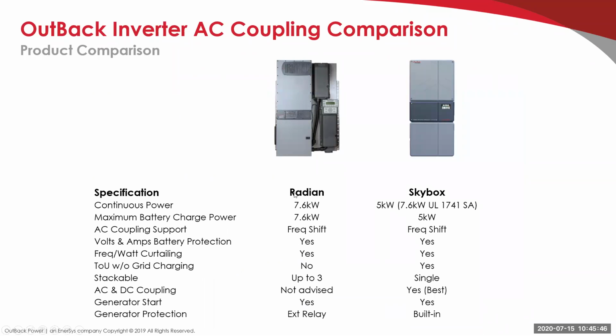So if we do a side-by-side comparison, continuous power, we can do 7.6 kW. There's a lot of those grid-dependent inverters out there. That limit is 5 kW with Skybox, unless it's a UL 1741 SA, where we can employ the frequency watt function to keep anything over 5 kW backed off. Maximum battery charge power, 7.6 versus 5 kW. That's in the off-grid mode. They both use frequency shift. They both protect the batteries with voltage and current protection, frequency watt curtailing, time of use without grid charging.